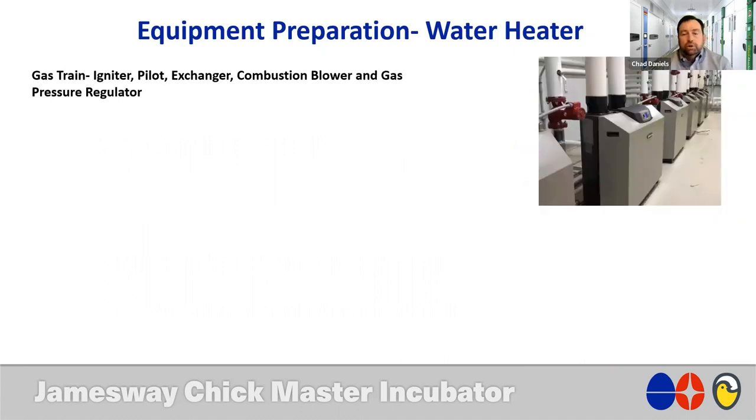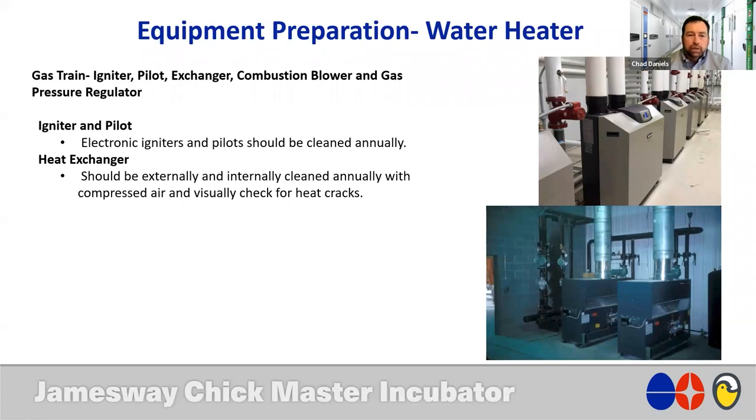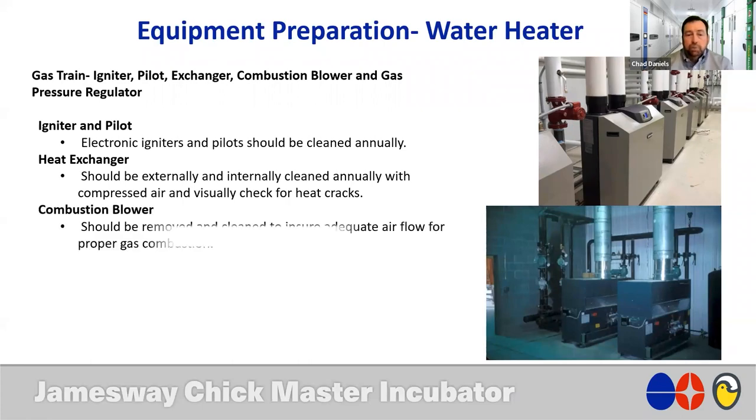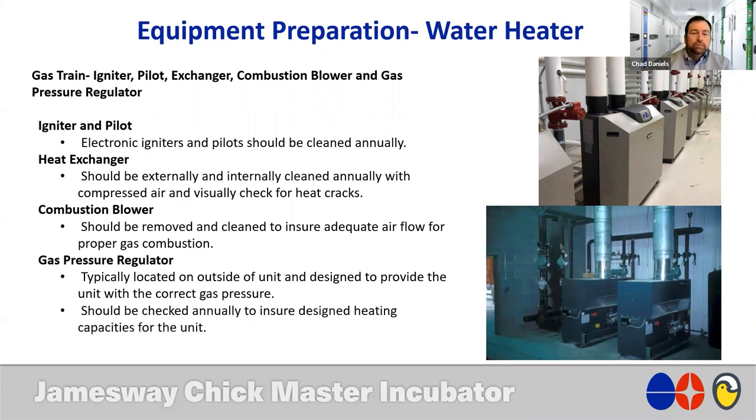So let's talk about water heaters. You may have a system where you have multiple small water heaters, or you may have a boiler room where you have a couple of larger hot water heaters. In either case, again, you have the same thing we talked about with the HVAC. You've got the igniters and pilots, the heat exchanger, combustion blower that should be removed and cleaned, and again, the gas pressure regulator that has to be checked for the pressure in order for that to provide you with the designed heating capacity of the unit. So it's important, again, with these units, in order to provide the capacity you need, to make sure you check these items on your hot water heaters and your boilers.